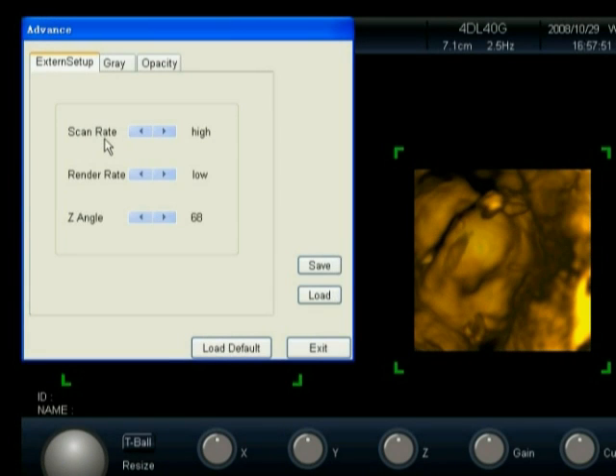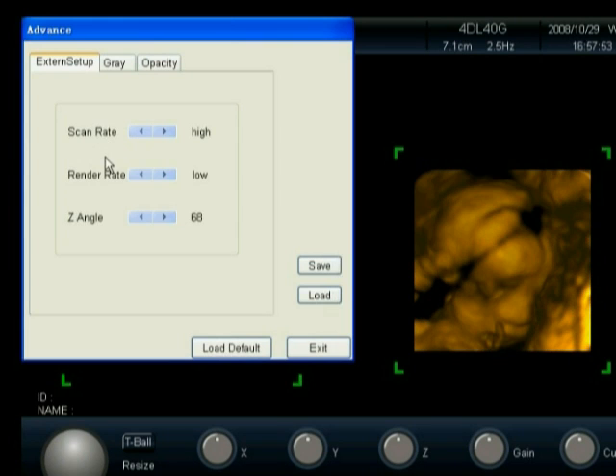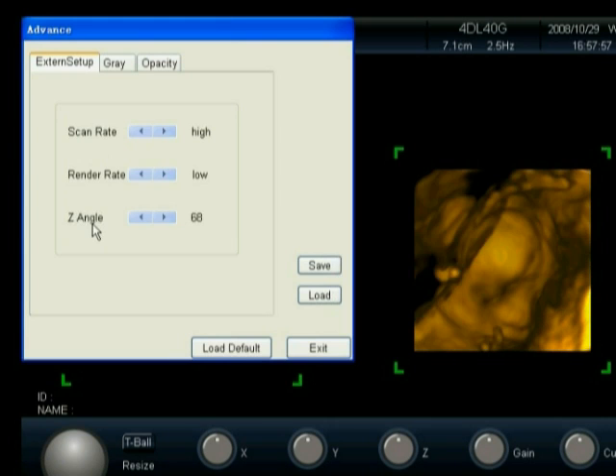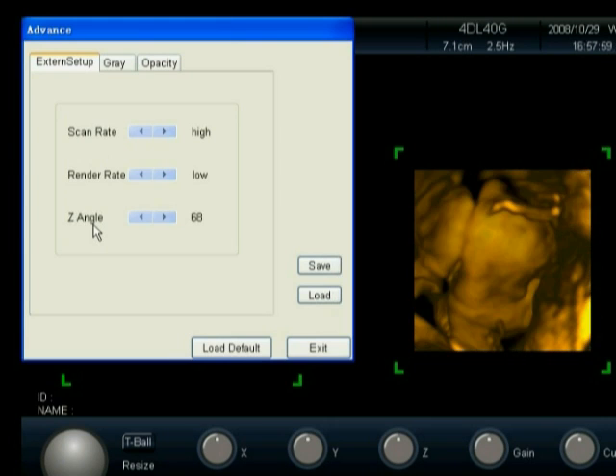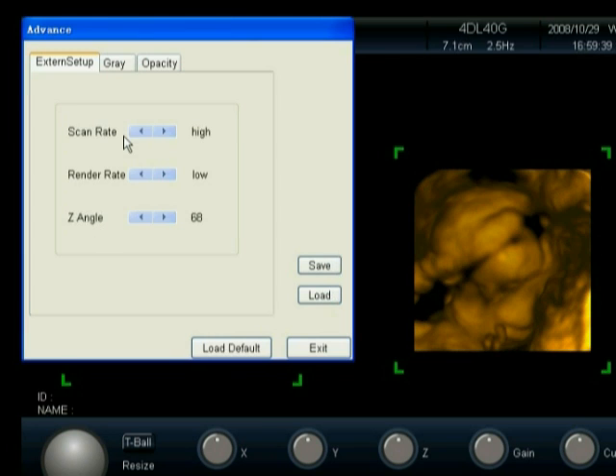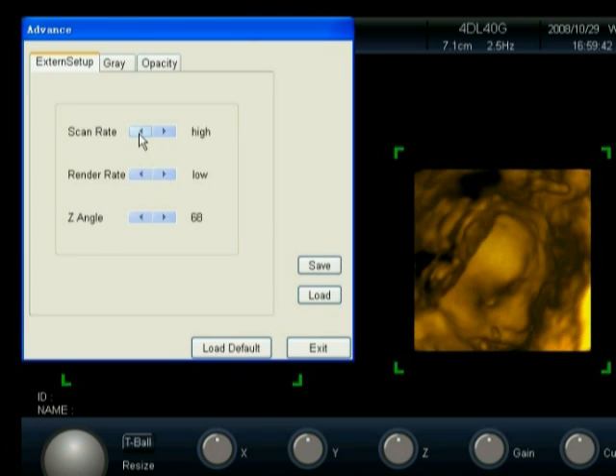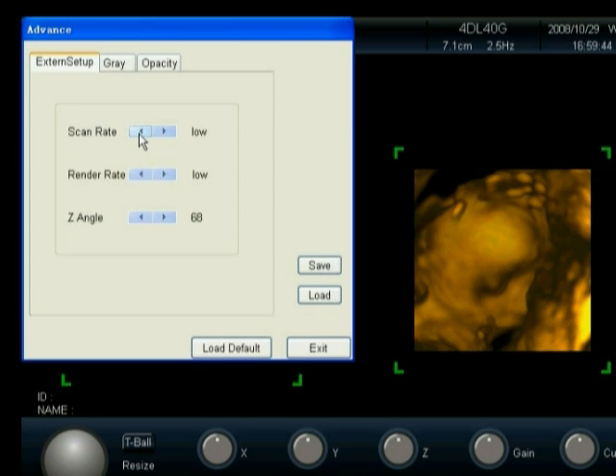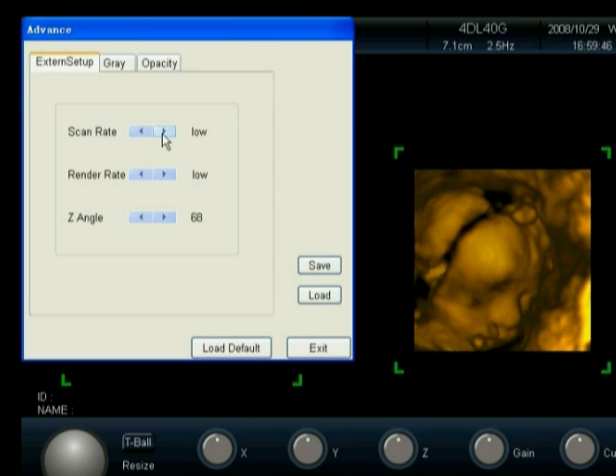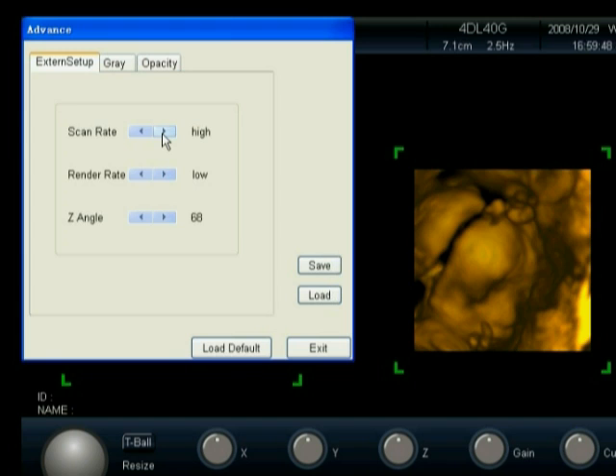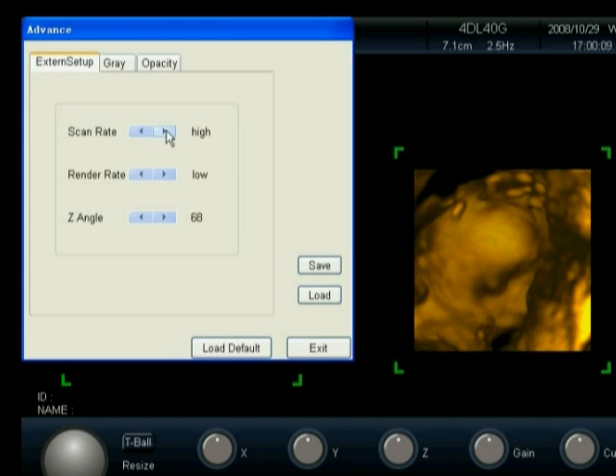In Advanced Setting, go to the tab ExternSetup, and you may adjust image acquisition speed, image rendering speed, and scanning angle along axis Z. Increasing image acquisition speed will improve 4D image real-time performance, but the imaging quality will be lowered a little bit. It is recommended to use high-speed acquisition.